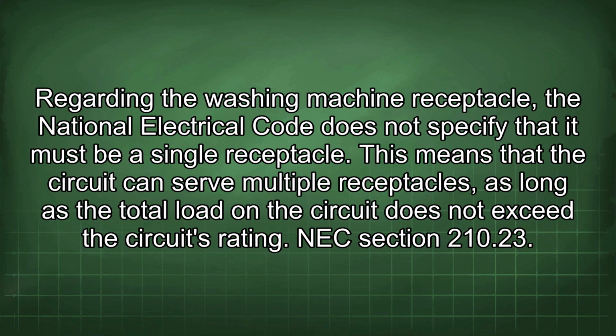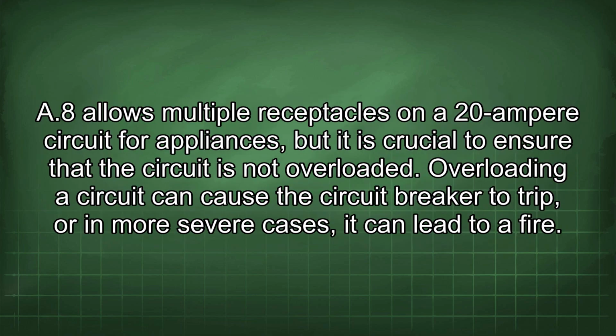Regarding the washing machine receptacle, the National Electrical Code does not specify that it must be a single receptacle. This means that the circuit can serve multiple receptacles, as long as the total load in the circuit does not exceed the circuit's rating. NEC Section 210.23(A)(8) allows multiple receptacles on a 20 ampere circuit for appliances, but it is crucial to ensure that the circuit is not overloaded. Overloading a circuit can cause the circuit breaker to trip, or in more severe cases, it can lead to a fire.